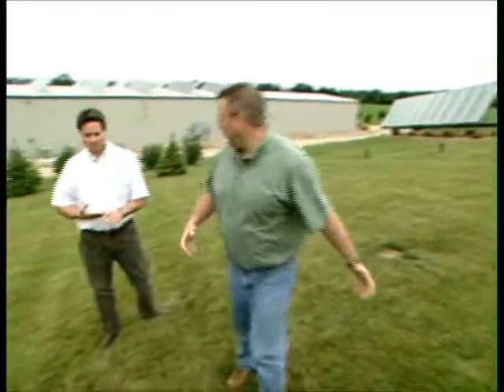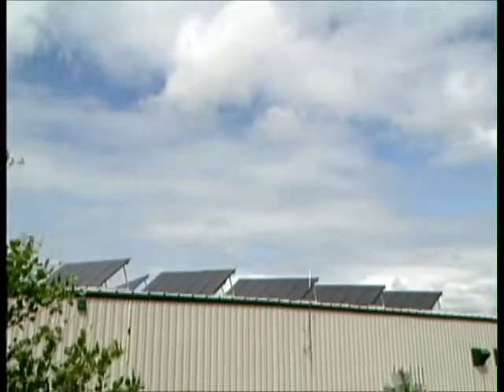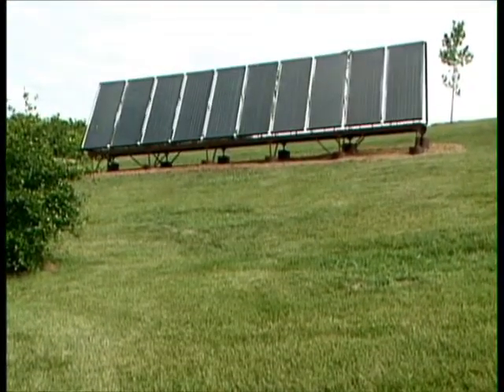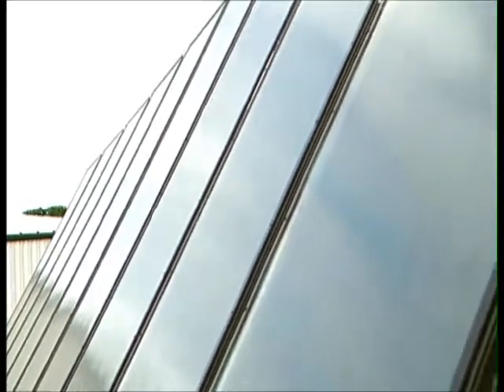Well, Kurt, it appears that this business is really taking advantage of solar technology. Stu, what we have here is a large photovoltaic system that's doing a great deal of the power for the facility, and a solar hot water system, and it's zoned particularly so that they can turn off certain zones in the wintertime and then use the solar to heat their primary zones. So are they going to realize a big decrease in fossil fuel usage? The solar domestic hot water system will do up to 80 to 100% of their domestic hot water needs, and it'll contribute between 20 and 50% of their heating depending on how the system's zoned.